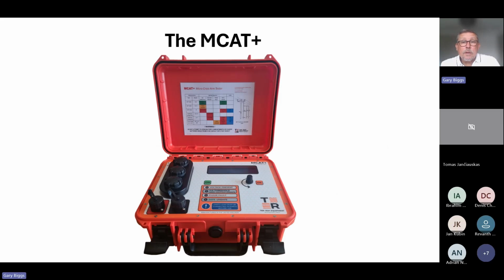This is the MCAT, how it looks. It's built into a very strong case, and the case itself, when the lid's shut, will be IP67 rated. There's nothing in the case of this instrument that changes the IP rating, so this unit can be carried around in all sorts of weathers, and in theory, if you dropped it into a lake or a river, it will float if the lid's shut.